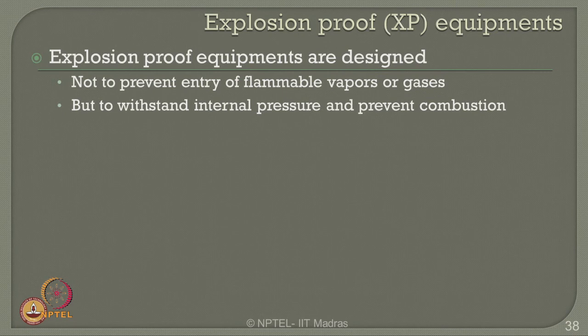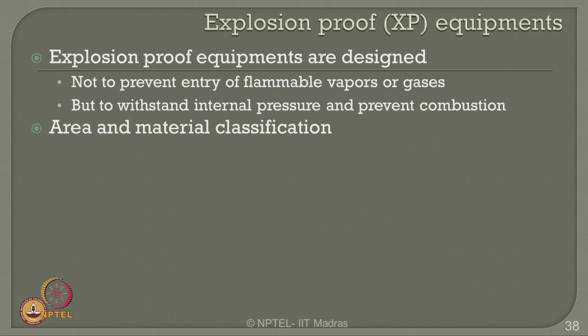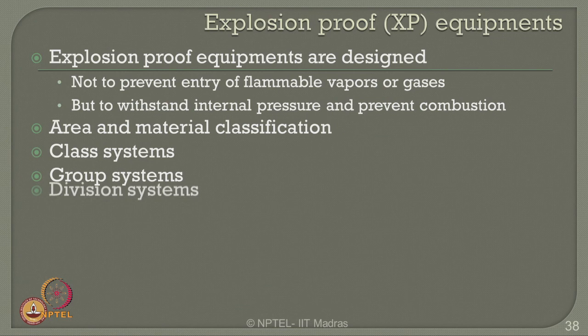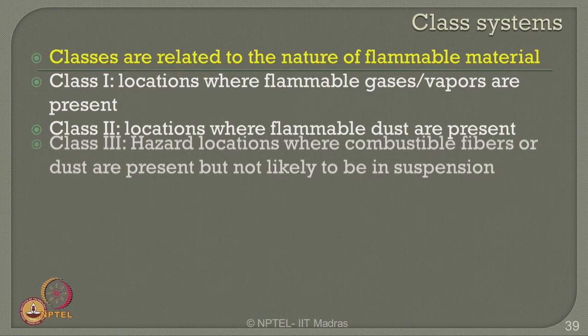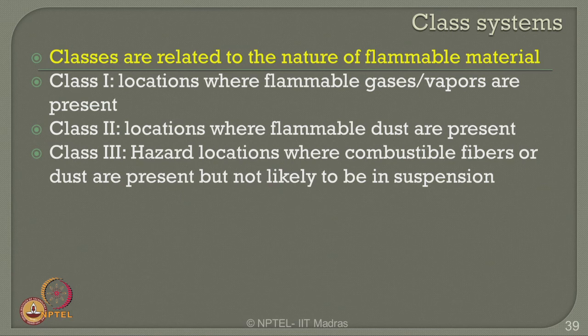One can also use explosion-proof equipment, rated as XP equipment. Explosion-proof equipment is designed not to prevent entry of flammable vapors or gases, but to withstand internal pressure and prevent combustion from these interactions. Area and material classification can be done as explosion-proof. Class systems are related to the nature of flammable material: Class 1 refers to locations where flammable gases and vapors are present, Class 2 where flammable dust is present, and Class 3 where combustible fibers or dust are present but not likely in suspension.